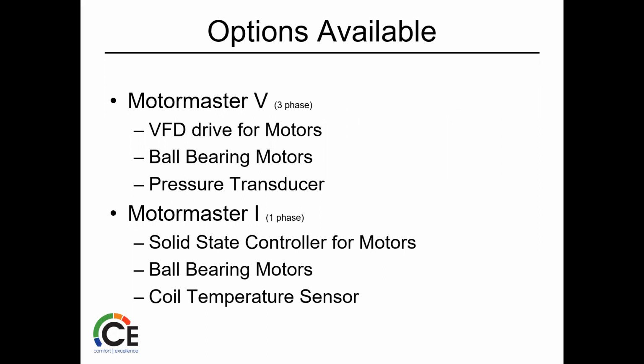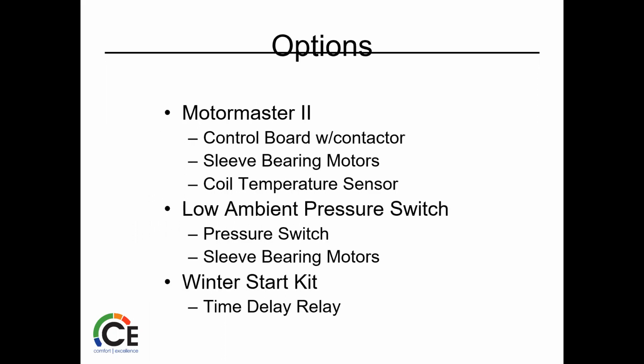You have MotorMaster 5, which is probably the most prominent one that's out there that helps with low ambient controls. There's a MotorMaster 1. We got a MotorMaster 2, which is a little different operation, just a basic low ambient pressure switch. So again, depending on what you got going on, what you really want to do, I'll try and breeze through these pretty quickly. But again, if you got questions, I'll keep checking the chat line. And then the winter start kit, which is your time delay.